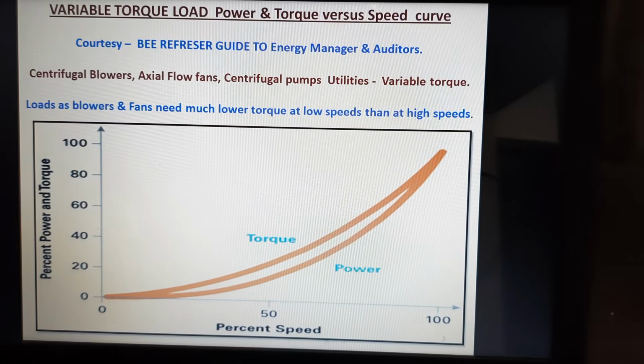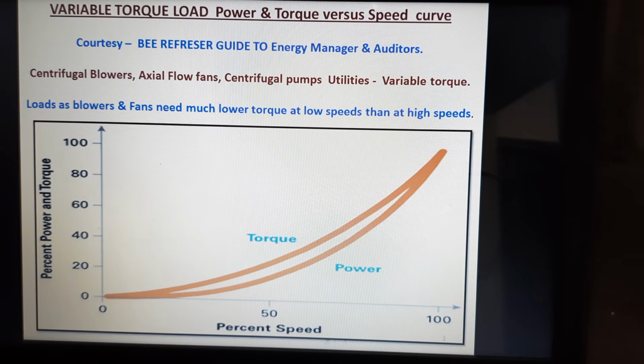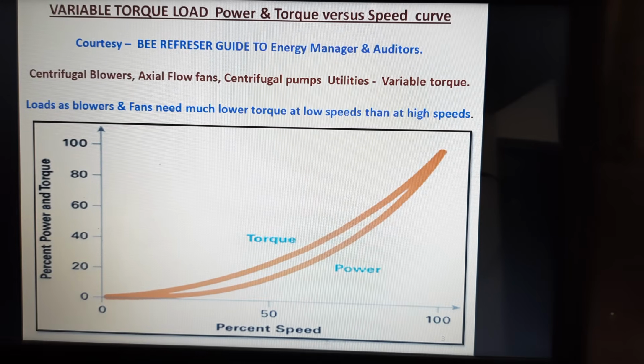Thanks to the Bureau of Energy Efficiency, the refresher guide for energy managers and auditors. You can see the curve, the graph of percentage speed versus percentage power and torque on any variable torque load. Maybe it is a centrifugal blower or an axial flow fan or a centrifugal pump in the utilities. These are all variable torque loads, and loads like blowers and fans need much lower torque at lower speeds than at high speeds. This is the focus area where you are trying to achieve the energy savings now.